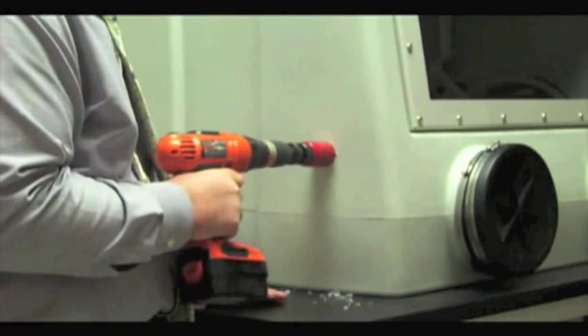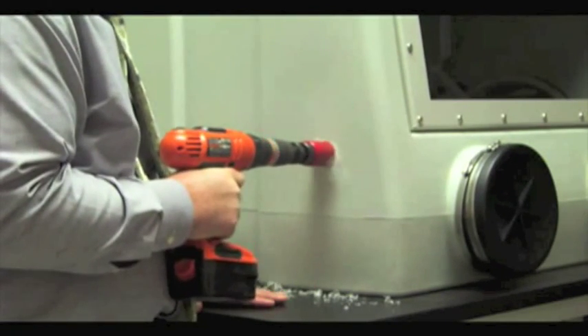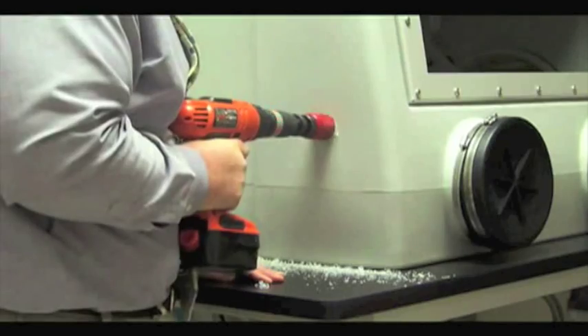The primary requirement for successful installation is selecting a flat wall location and keeping the hole saw parallel to the wall surface while drilling to avoid binding.